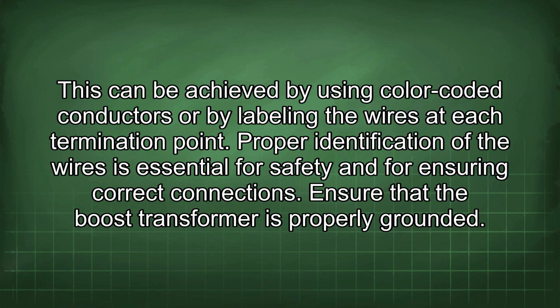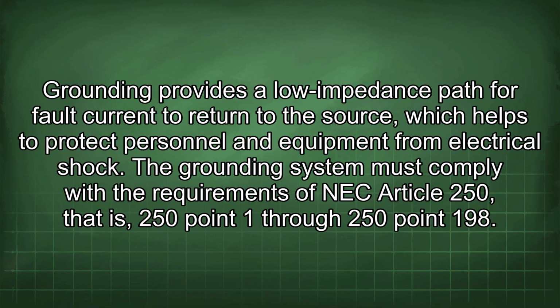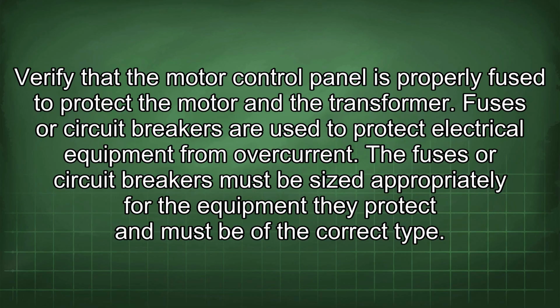Ensure that the boost transformer is properly grounded. Grounding provides a low impedance path for fault current to return to the source, which helps to protect personnel and equipment from electrical shock. The grounding system must comply with the requirements of NEC Article 250, that is 250.1 through 250.198. Verify that the motor control panel is properly fused to protect the motor and the transformer.